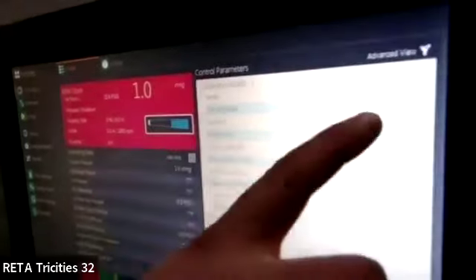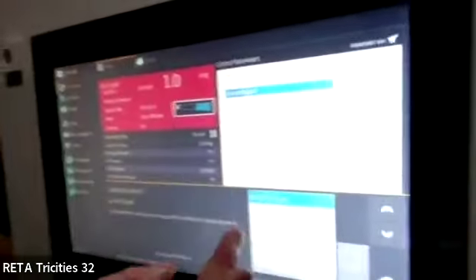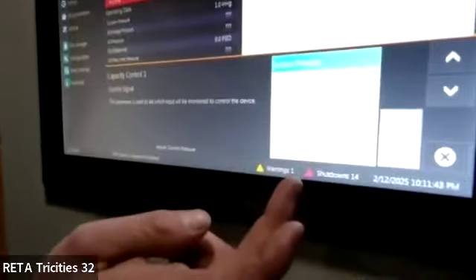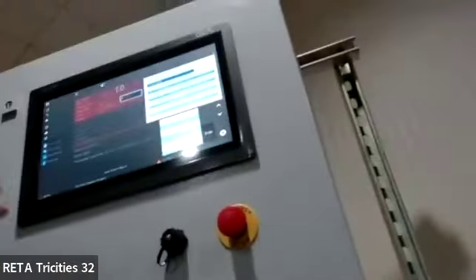So like this panel right now is enabled for 3 capacity controls. Basically you have capacity control 1 here, and you can do a control signal. You can run it off suction pressure, suction pressure as temperature, outlet temperature, inlet temperature, discharge pressure. You have a lot of different things you can actually run the compressor off of. Most of you guys, I'm assuming, unless you're running glycol chillers, are probably using pressure. A lot of people that run a glycol chiller are going to run their machine off of temperature, and they'll just go off of the outlet temperature of the glycol.